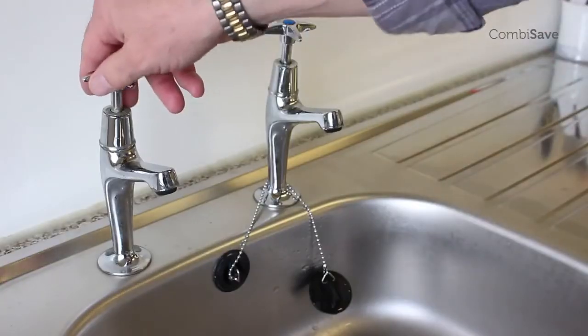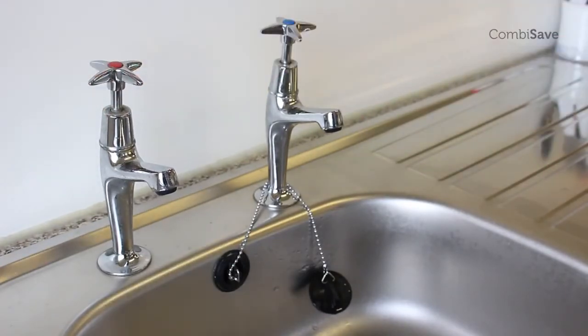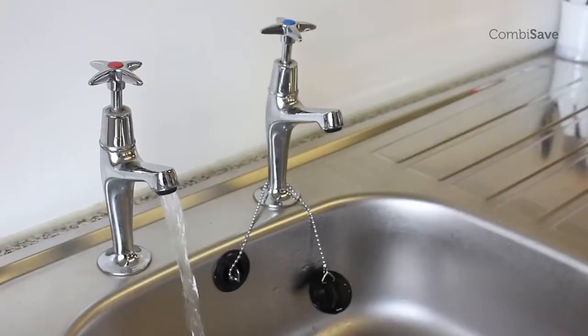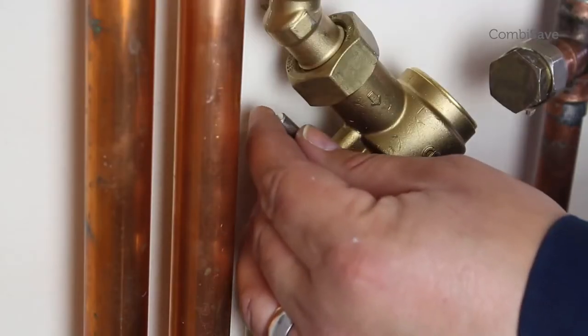When you turn on the hot water tap, no water should come out. Now slowly open the bypass screw until the boiler fires. Add an additional half a turn to the bypass screw and the CombiSave is now set.